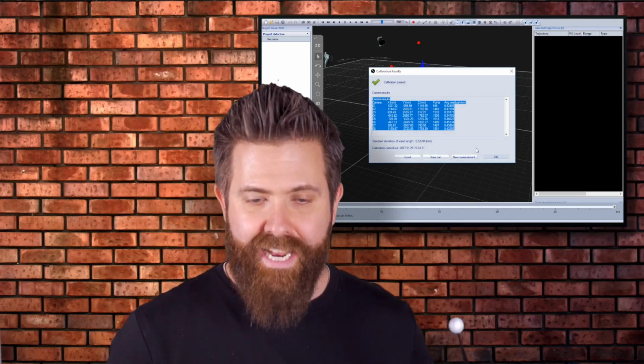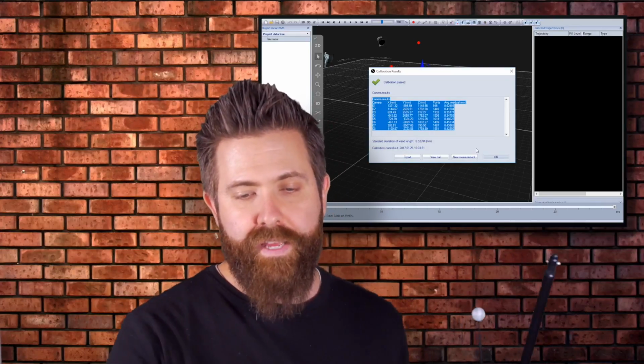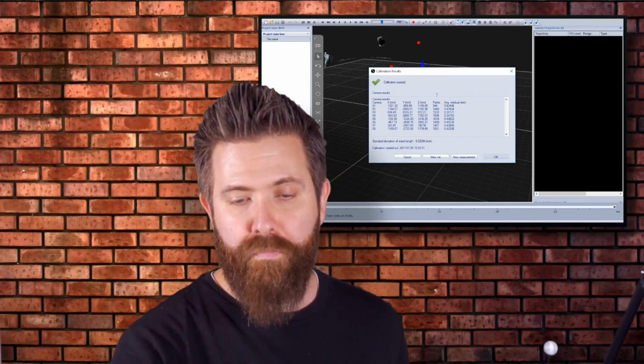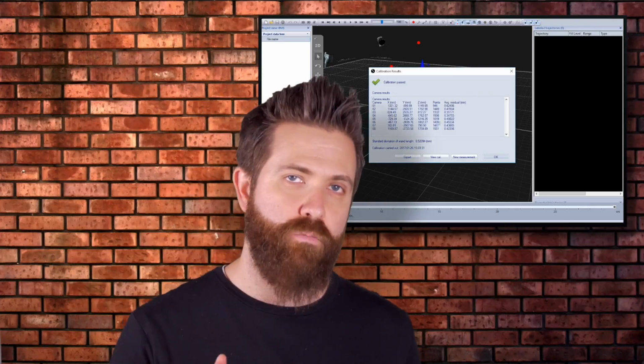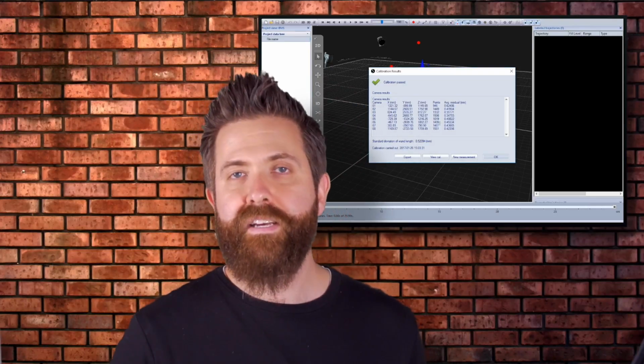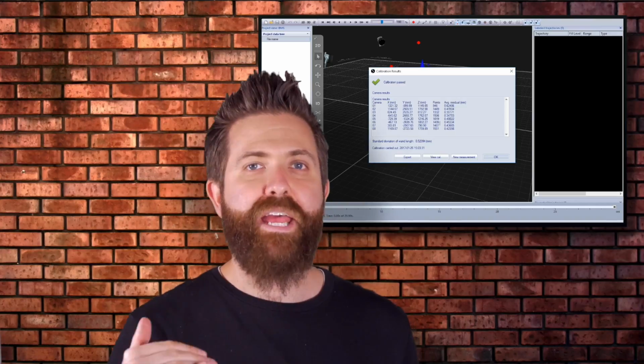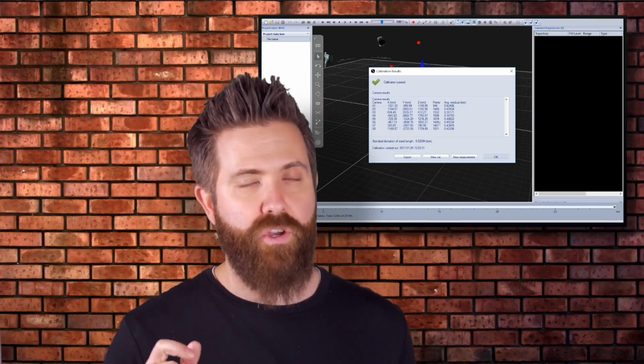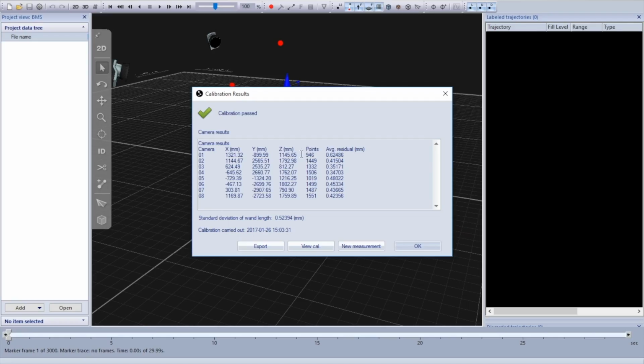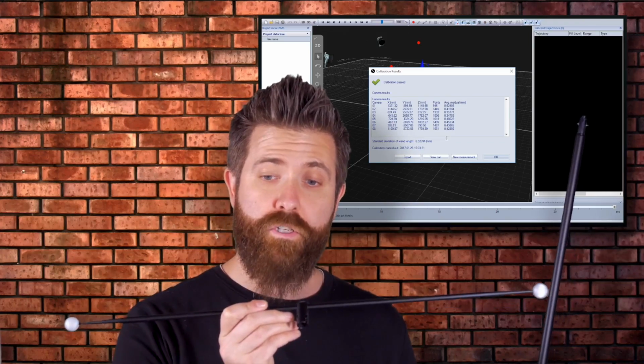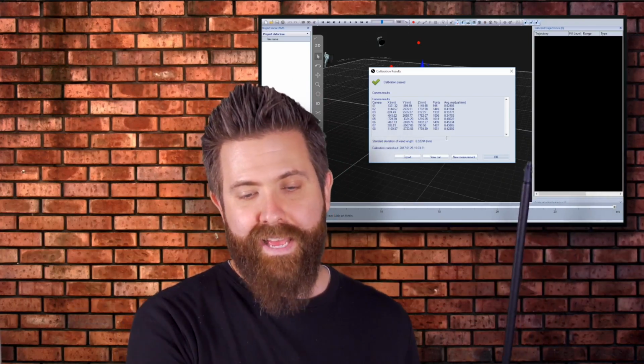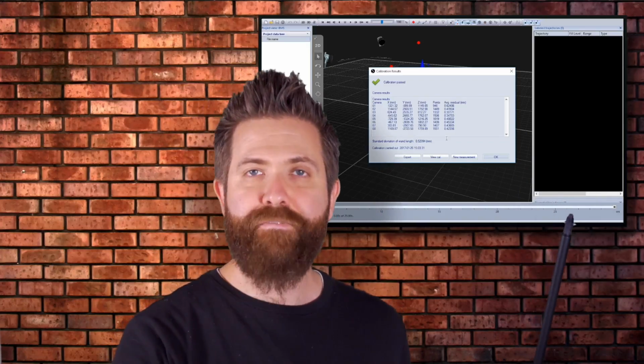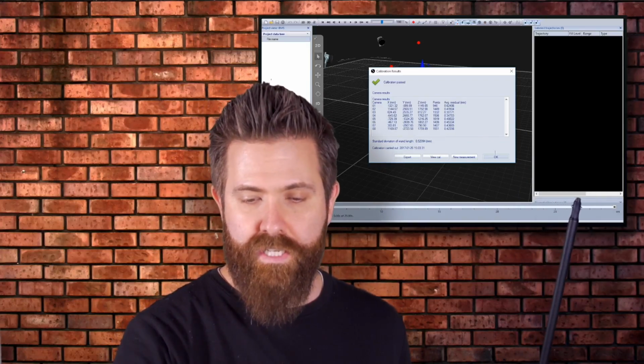Calibration passed, and as you can see, first of all, you see the number of points each camera sees. Very important that all the cameras have a minimum number of points, and that depends on the manufacturer. The most important thing I tend to look at is the standard deviation of wand length. That is the distance between the two markers on the wand. In this case, it's about 0.5 millimeter. That's a very good result.